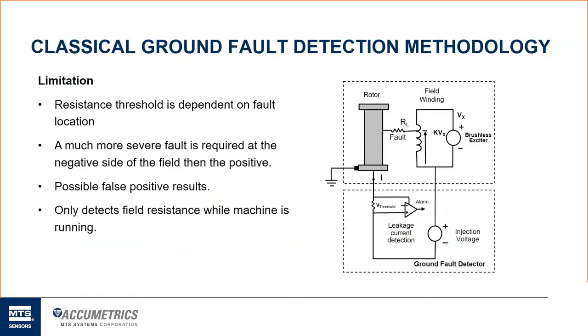So the classical ground fault detection method, as I was talking about before, is a DC injection voltage that they put out onto the exciter shaft itself, and that biases that negative side of the field slightly higher than rotor ground. It looks for that current leakage to go from the field windings to rotor ground. Then there's some circuitry with a threshold that's set out there to measure. If you have current and you have voltage, you can calculate using Ohm's law what the field resistance will be. And if the resistance drops below a certain threshold, it'll trigger the alarm. In most cases, as I mentioned earlier, that's a single point threshold set at 10K ohms.